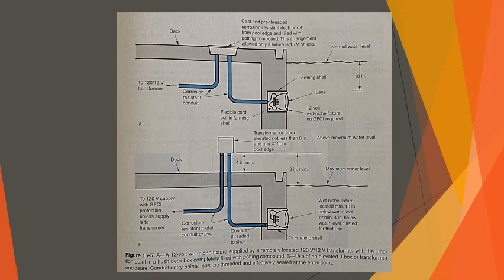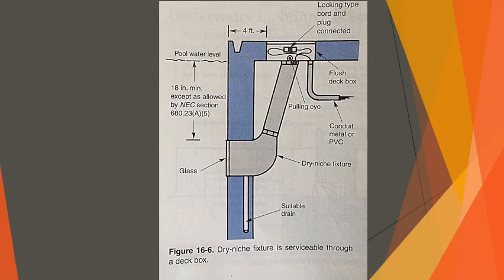Dry niche fixture. The dry niche fixture is an underwater pool light that is installed inside a watertight enclosure within the pool wall. This type has a drainage pipe provided so that any moisture will be removed. A deck box is required and must be installed flush with the deck surface at a minimum of 4 foot from the pool edge. This deck box is where the dry niche fixture is connected to the electrical supply. The dry niche fixture is illustrated in figure 16-6. Notice the cord and the plug connection and large deck box for maintenance, repair, and relamping.